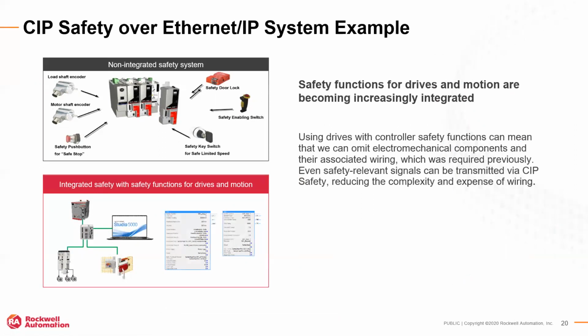So the top picture there shows a traditional non-integrated system with standard safety interlocks, safety push buttons, enabling switch, encoders. All those items are hardwired back to either safety monitoring relays or to the safety controller I/O. So there's a lot of wiring that's being done. If you have to make a change, you've got to go out and do the hard wiring there.